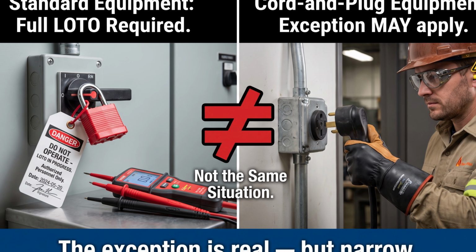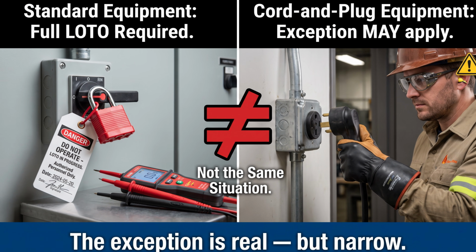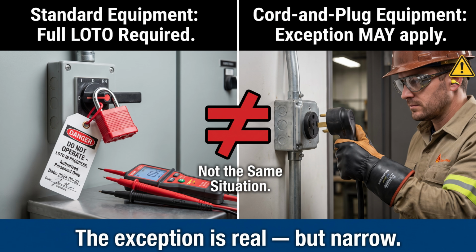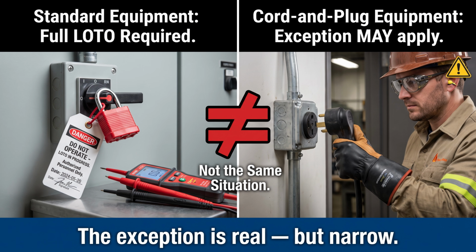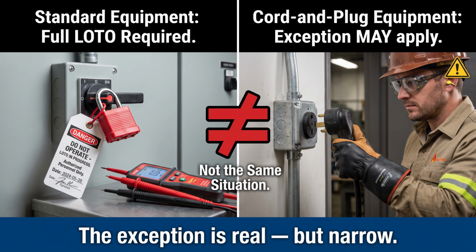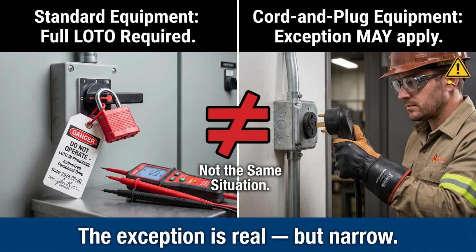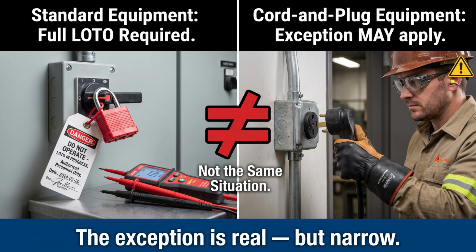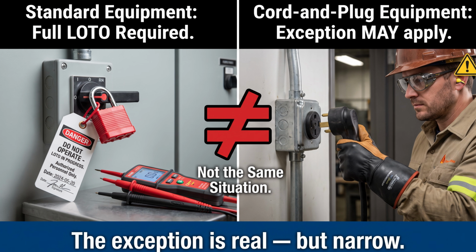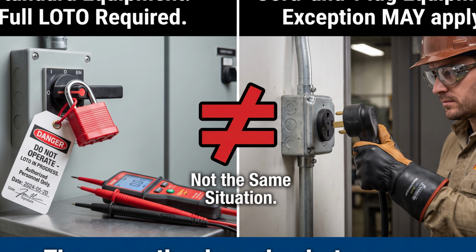OSHA's Lockout Tagout standard contains a specific exception for cord and plug connected equipment. If the equipment is connected by a cord and the plug is under the exclusive personal control of the employee performing the service or maintenance, full lockout tagout procedures are not required. But the word exclusive is doing enormous work in that sentence. Let's break down exactly what it means and where the boundaries are.